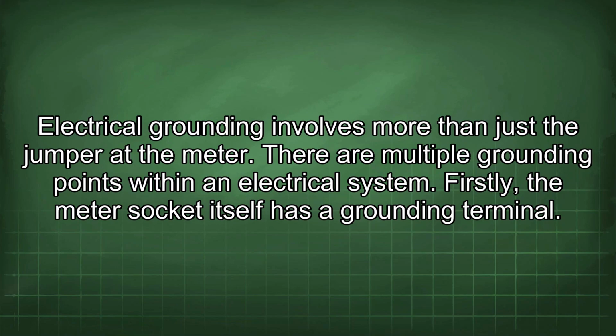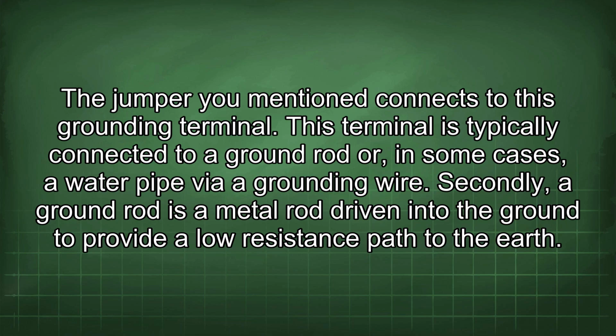Electrical grounding involves more than just the jumper at the meter. There are multiple grounding points within an electrical system. Firstly, the meter socket itself has a grounding terminal. The jumper you mentioned connects to this grounding terminal. This terminal is typically connected to a ground rod or, in some cases, a water pipe via a grounding wire.